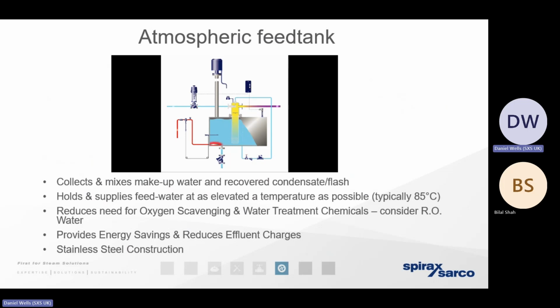The sweet spot is really 85 degrees. Any higher than 85 degrees, and some of that hot water is likely to boil off and produce steam as it falls in pressure when it's drawn across the boiler pump. It's going to create quite an expensive problem for our client. That's why we vent any excess of energy away from the hot well to prevent that over temperature. But if it's any lower than 85 degrees, then we've got to burn more gas. Our cost of steam and our carbon emissions are going to increase.